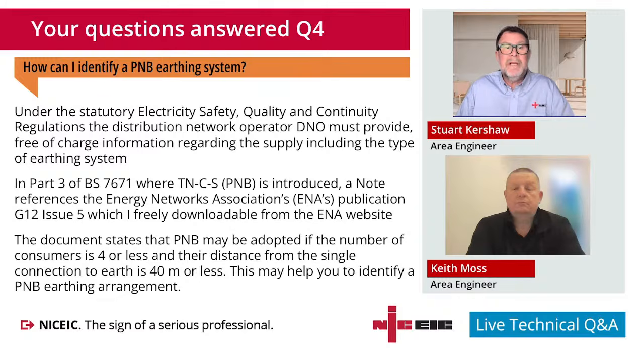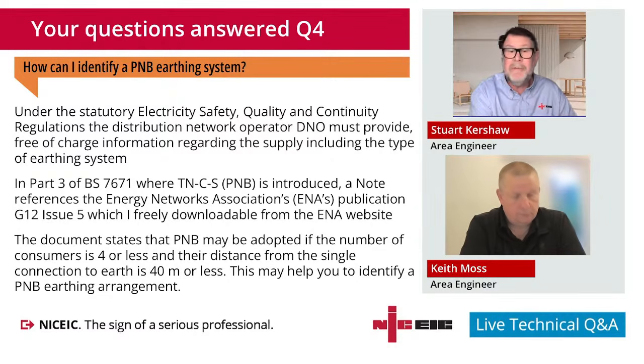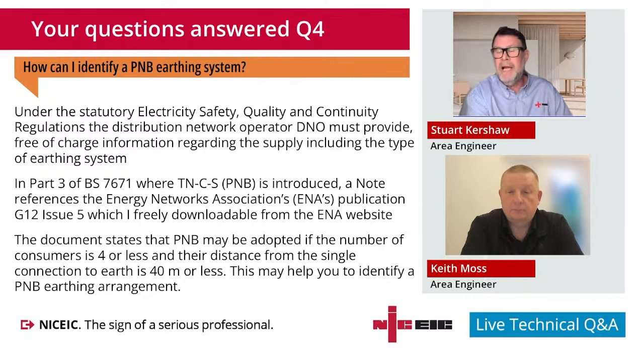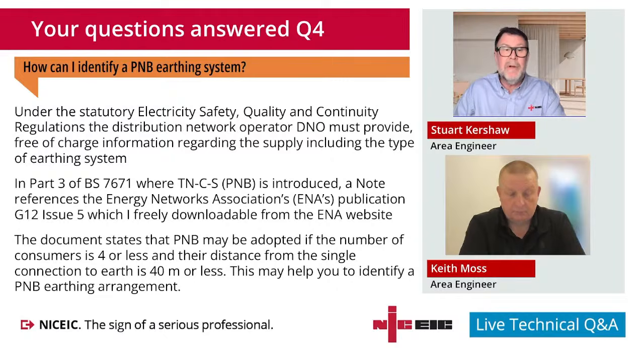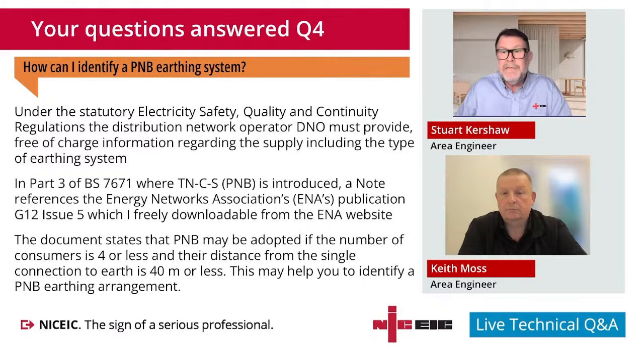And the reason for PNB is that in some properties, maybe fed from a small pole-mounted transformer or similar, where it serves 4 properties or less, there would be a chance that it could be PNB. You can reference the Energy Networks Association's G12 document for more information, particularly sections 3.15 and 4.11. It states that PNB may be adopted if the number of consumers is 4 or less, and within a distance of 40 metres or less from the transformer or substation serving those properties.